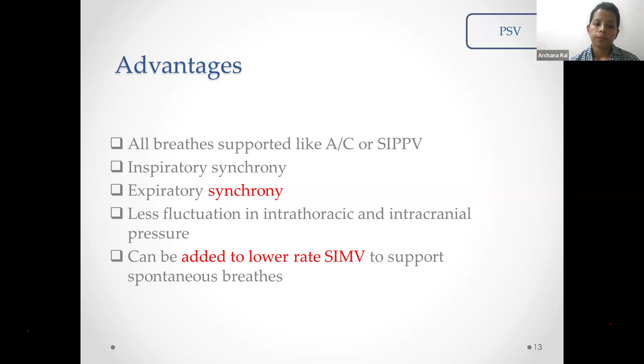It is helpful with the SIMV mode when we are weaning the baby from the SIMV mode and gradually tapering the set rate of the SIMV mode. When the rate is less than 30, many of the breaths will not be supported. At that time, if we add the PSV mode, those breaths will be supported, and thereby we will have a better VT rather than only using the SIMV mode.